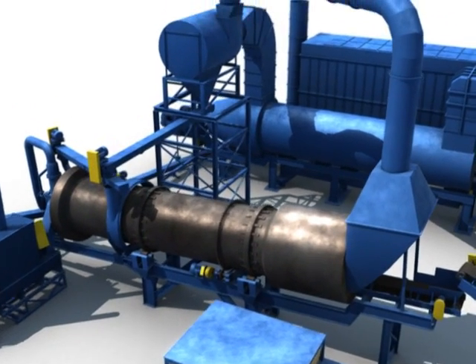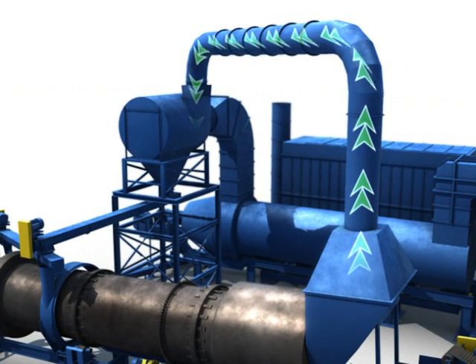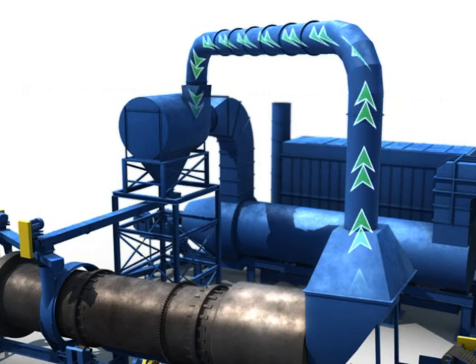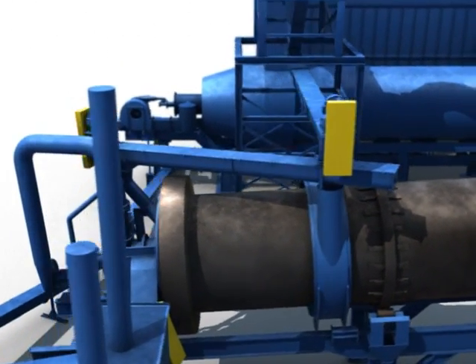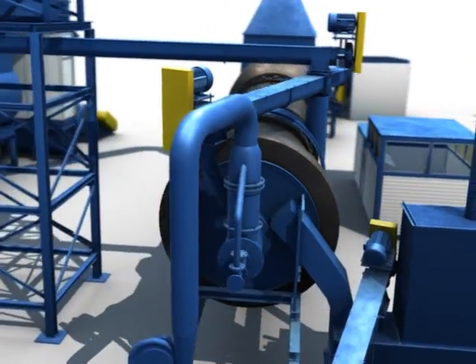Using a 50 million BTU Hauck burner, the hydrocarbons move up the ductwork to the cyclone. The cyclone separates the heavy end of dust from the hydrocarbon airstream. The dust is then deposited via augers into the desorber's direct flame for reburning. This patented process, in essence, will help achieve burning temperatures of 1,100 to 1,200 degrees.